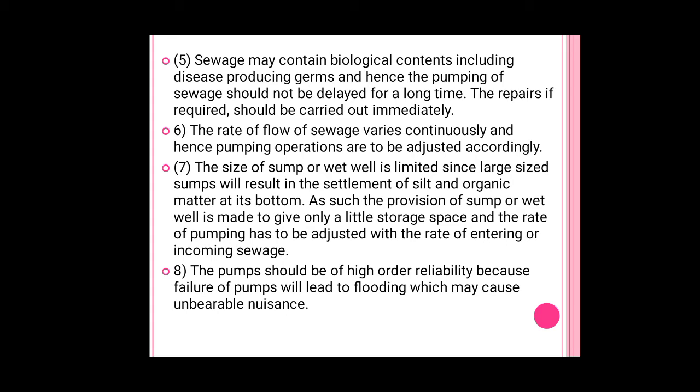When the size of the sump or the well is limited, since a large size sump will result in settlement of the silt and organic matter at its bottom. As such, the provision of the sump or wet well is made to give only a little storage space, and the rate of pumping has to be adjusted with the rate of the incoming sewage.